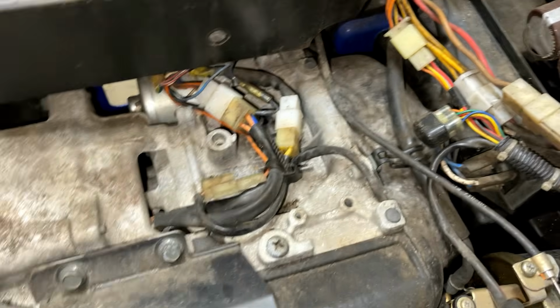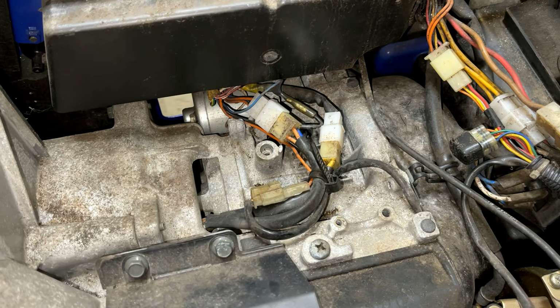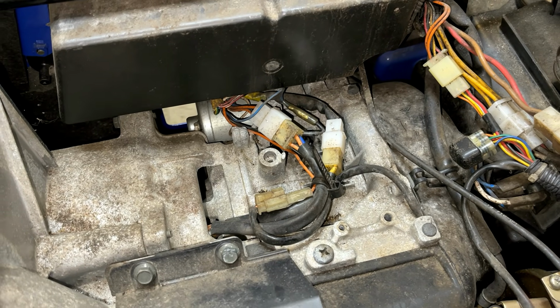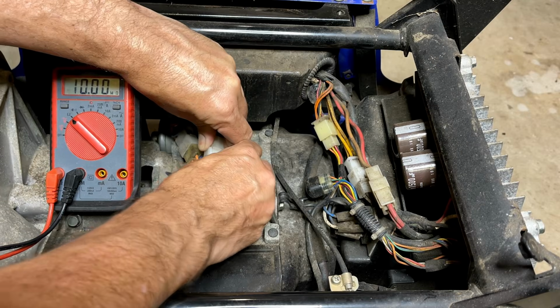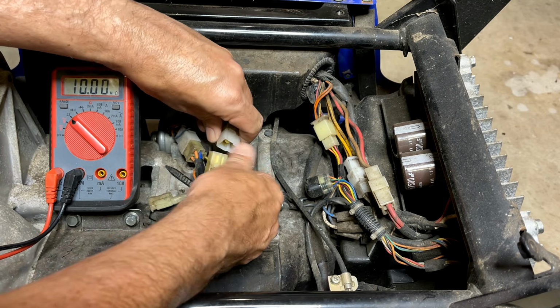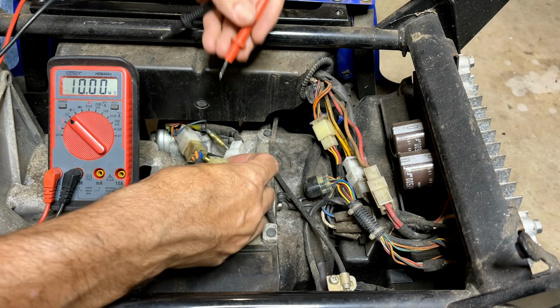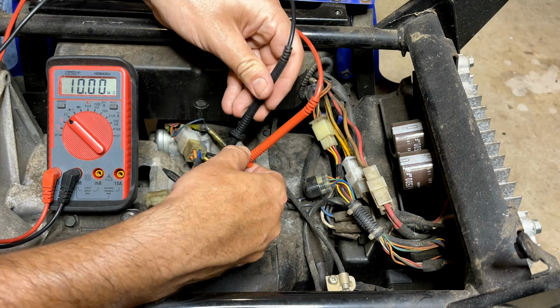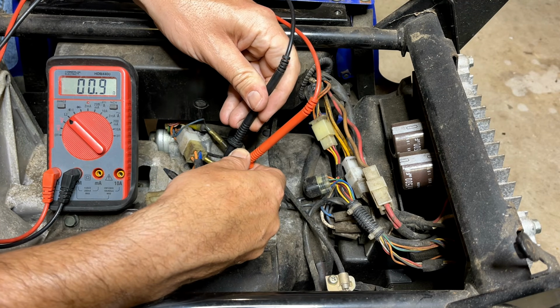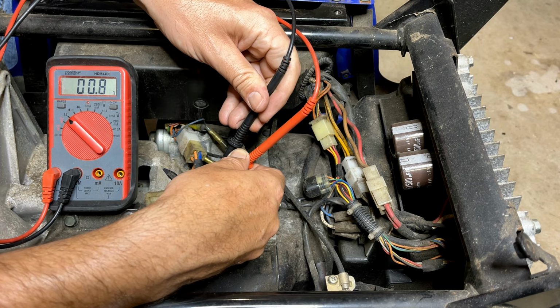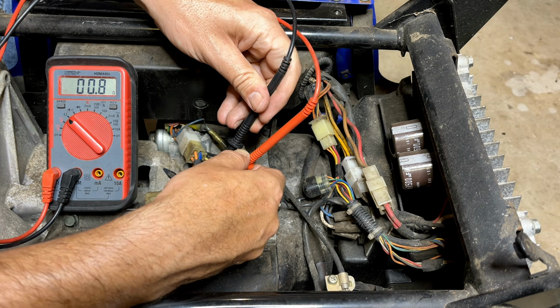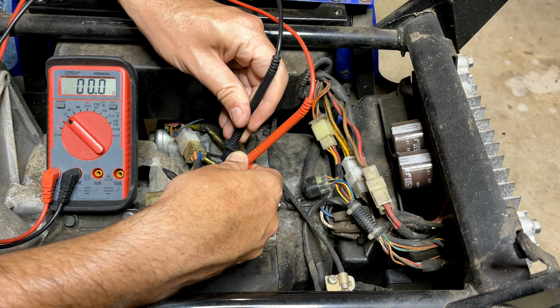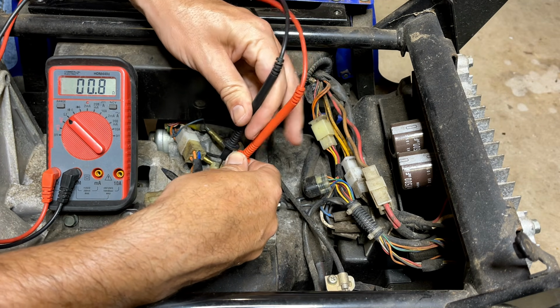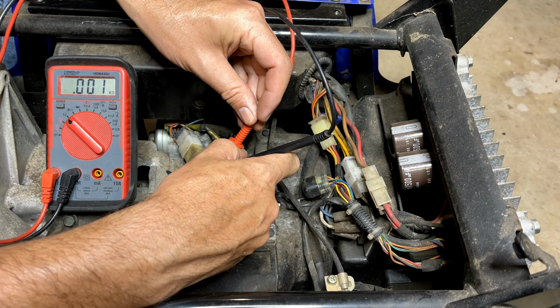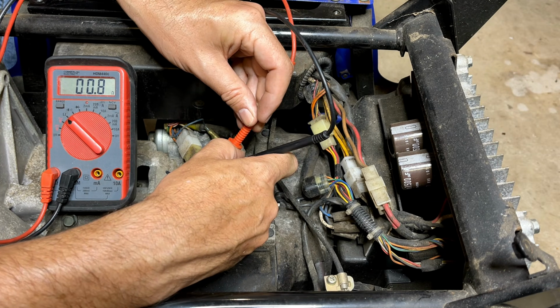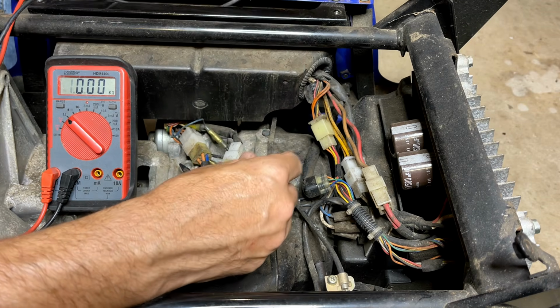Let's get the meter on the stator wires and see where we're at as far as resistance goes. On this leg we're at about 0.8 ohms. Leg 2, the same. And same on leg 3. So that appears to be good.